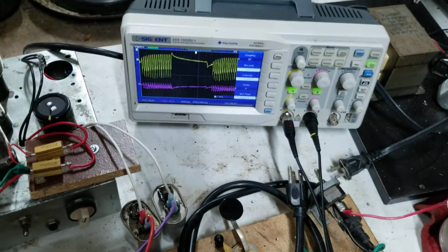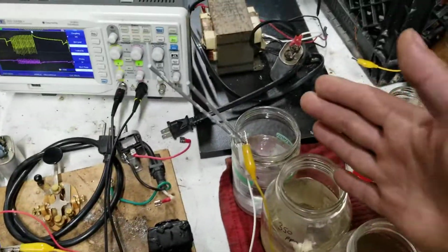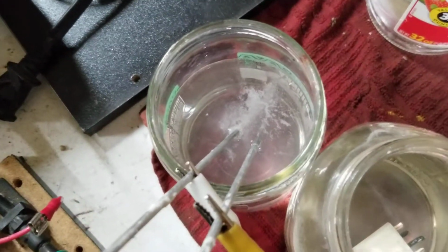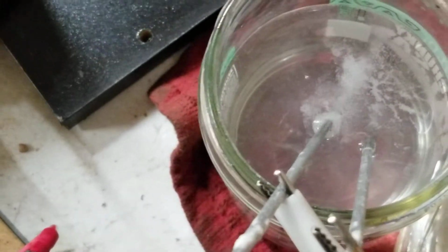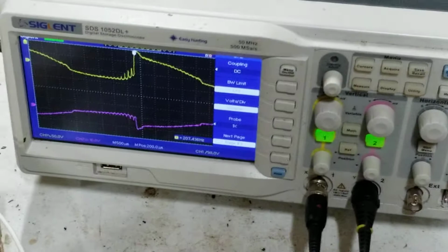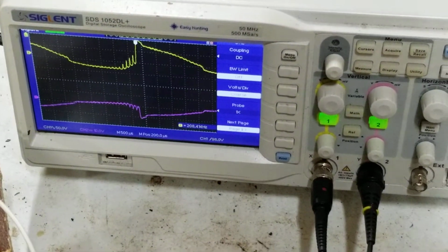So the scope is reading on the inside of, basically against the cell. So it's right on the cell. And here we see with the 10 ppm what looks like just the single electrode mainly, but there is some coming off a small amount on the other one. So if I take this out, you see my waveform goes away.